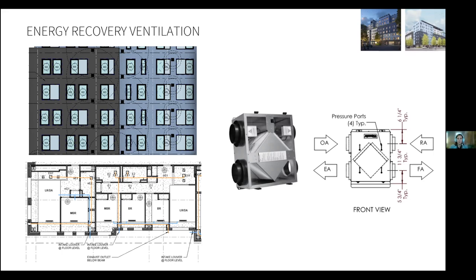So at both Linden 2 and 3, the owner preferred unitized ERV equipment in each apartment, shown here, rather than a vertical centralized system. Also, while we do have adequate overhead height within the units to accommodate these smaller branches of horizontal ductwork for the unitized system, we did not have available height for larger overhead transfers that are often required for a centralized system when they connect to the units at the rooftop. So we located these unitized ERV equipment in small enclosures within each apartment along the exterior facade to minimize the insulated run of ductwork to the fresh air intake. The more challenging piece of this unitized rather than centralized strategy has been coordinating through-wall penetrations and maintaining adequate distance between the exhaust and fresh air intake louvers and operable windows.